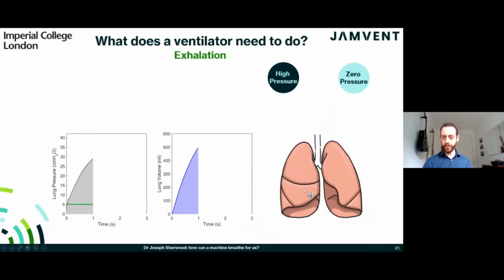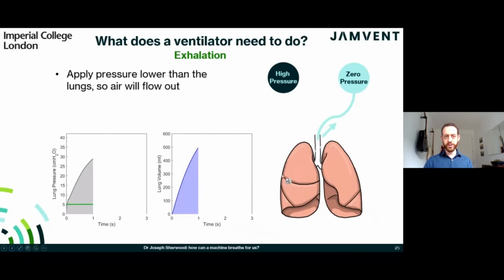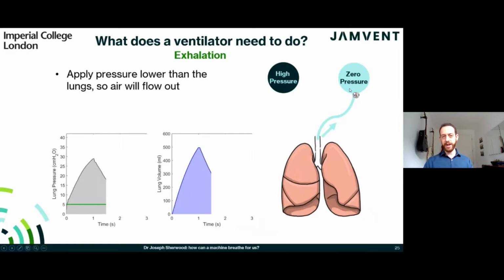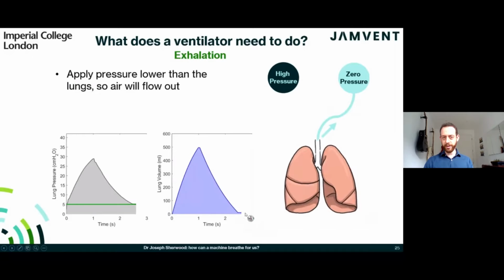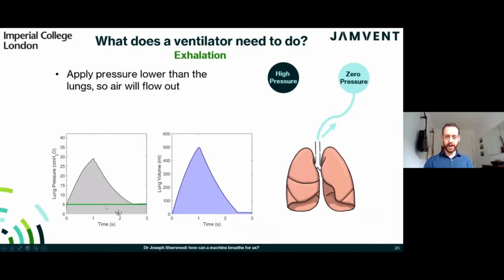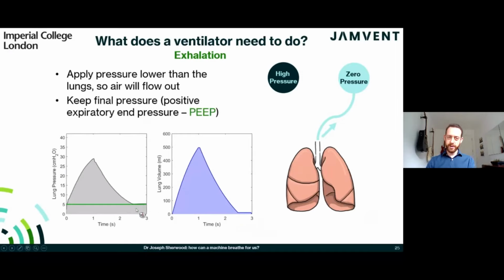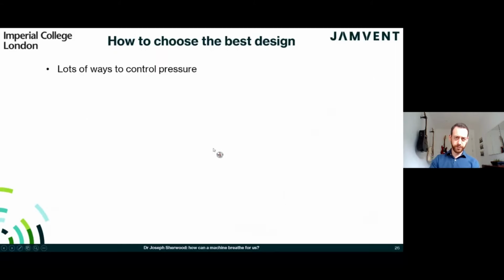To exhale, once we've got the large lungs, we connect to a low pressure area to set up a pressure gradient in the opposite direction, and the volume comes back down to baseline. The pressure doesn't go to zero though - we keep it slightly above zero at a level called the positive end-expiratory pressure, or PEEP, to make sure the alveoli stay open, maximizing that large half-tennis-court surface area.